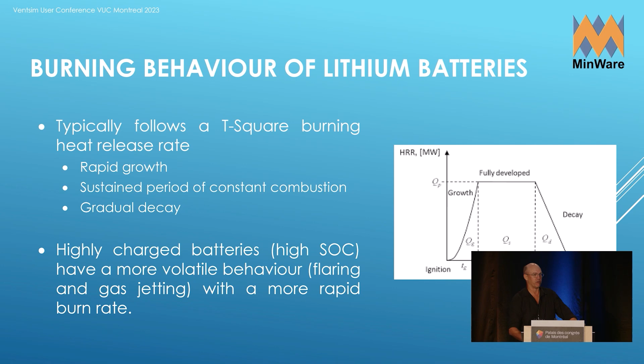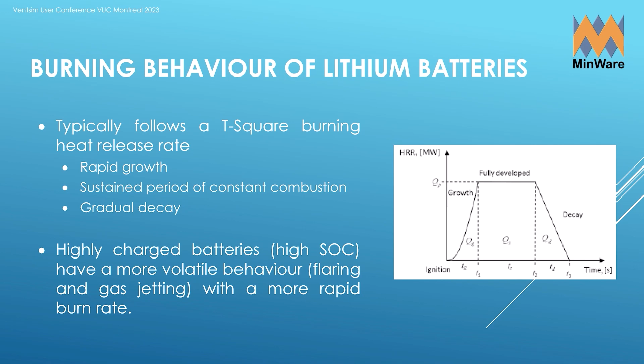When batteries burn, we've seen enough battery tests on surface vehicles to know they follow what's called a T-squared curve - time-squared curve. The battery fire ramps up, burns continuously for a period, and when the fuel runs out, it slowly decays and burns out. As said before, highly charged batteries, or high SOC (state of charge), tend to have more volatile behaviour, but the amount of heat released is very similar.